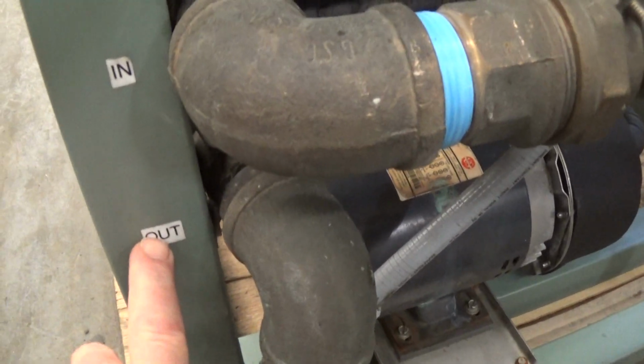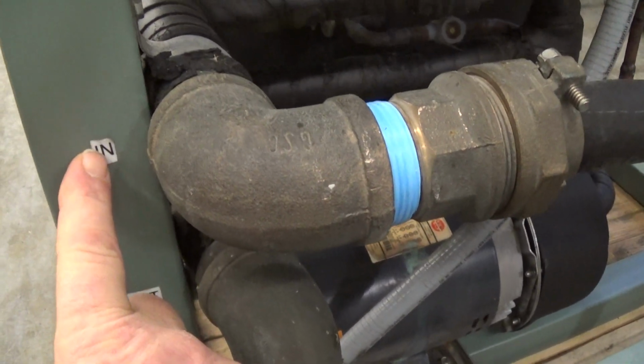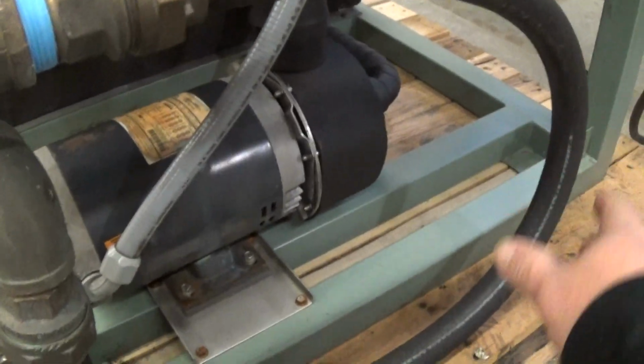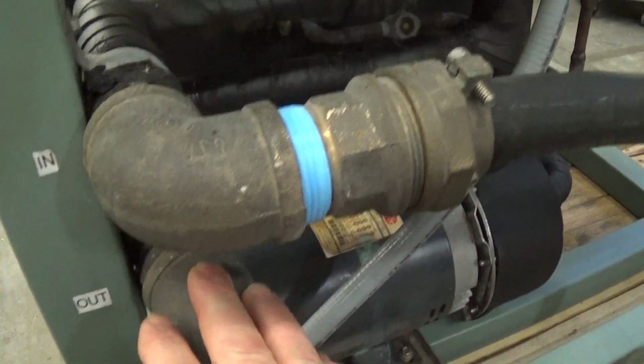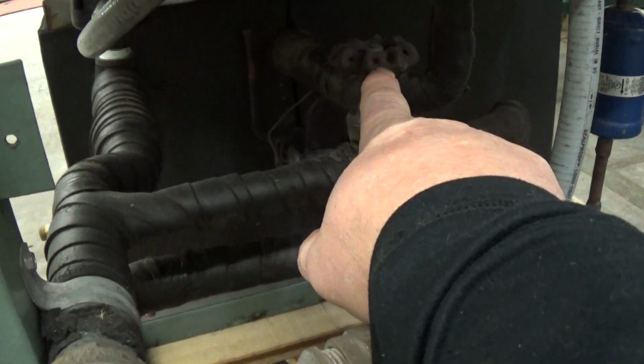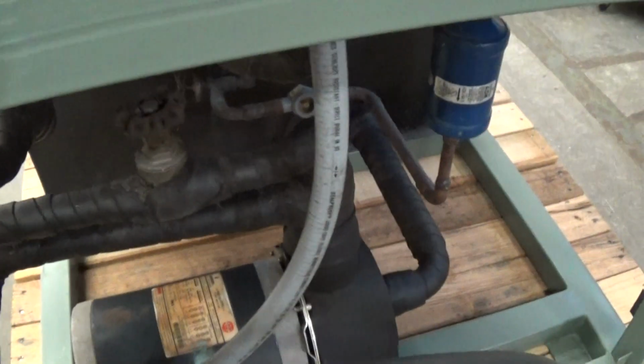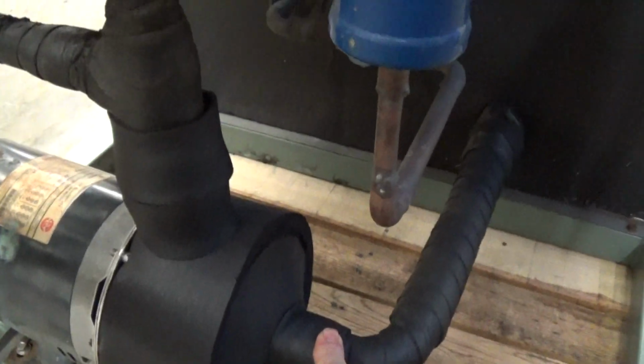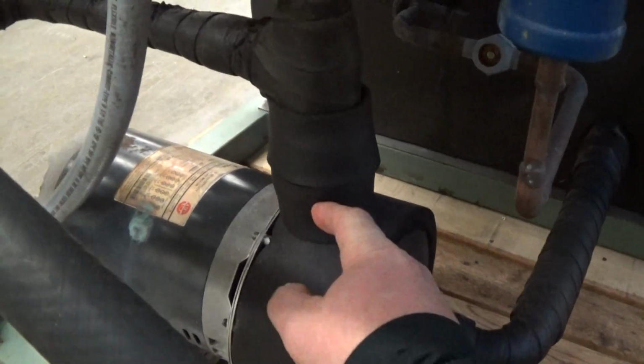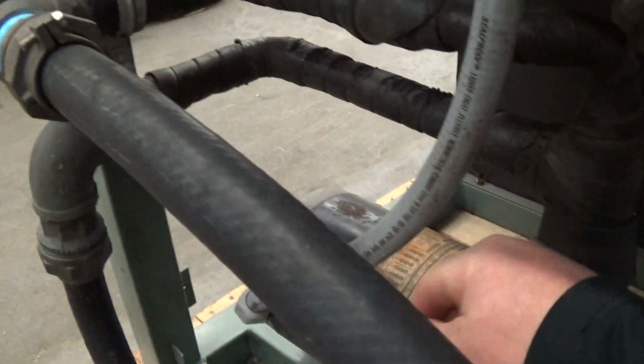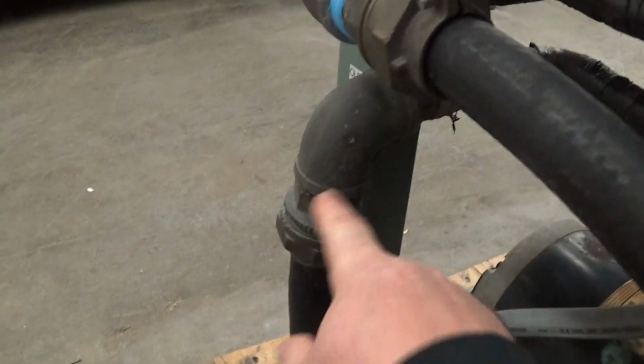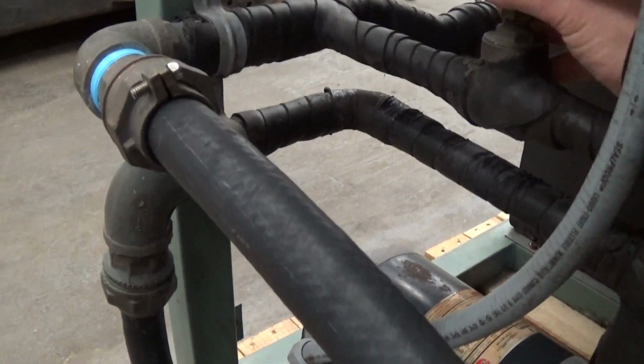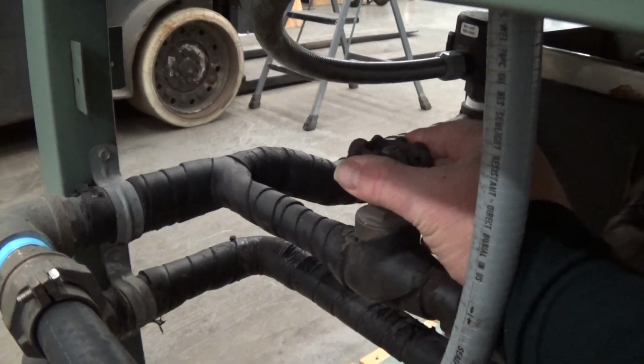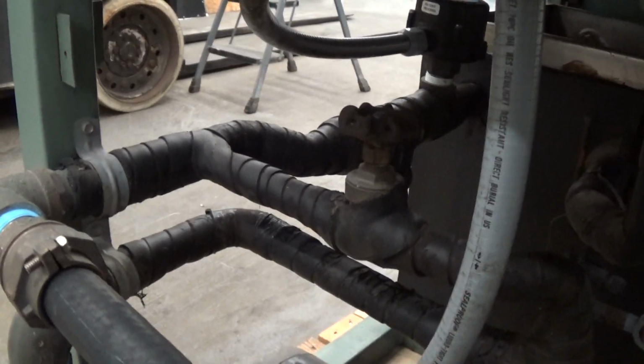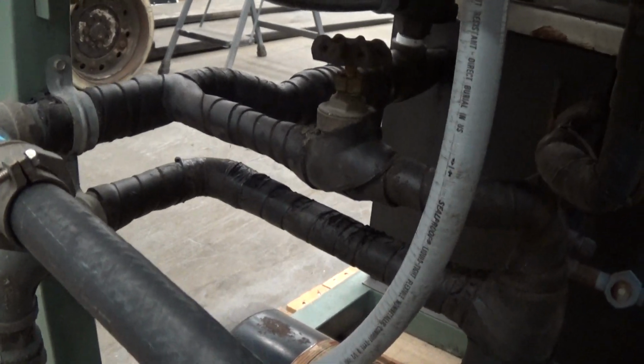This is your out from process. This is your in. This is our test loop right here. This here is your bypass. So the pump draws from our reservoir tank, discharges up and out to your process here. We're going to ship this bypass opened about halfway. Ultimately, you may need to adjust that in the field.